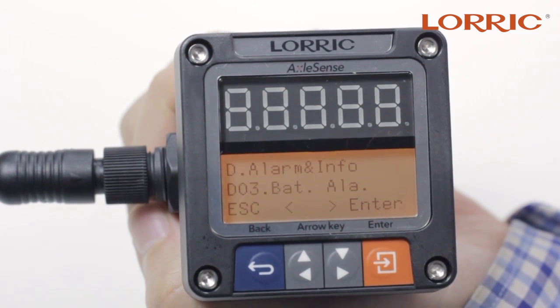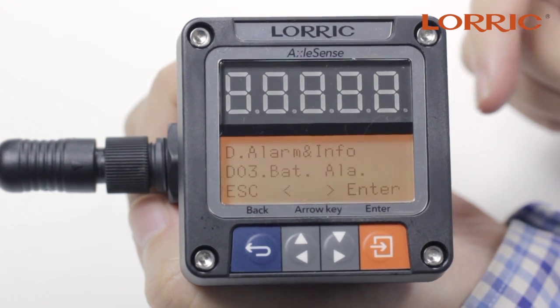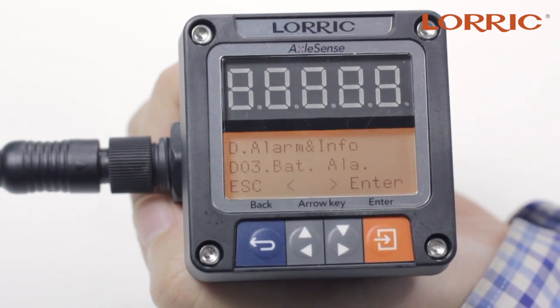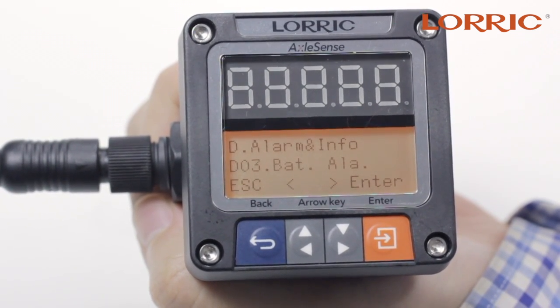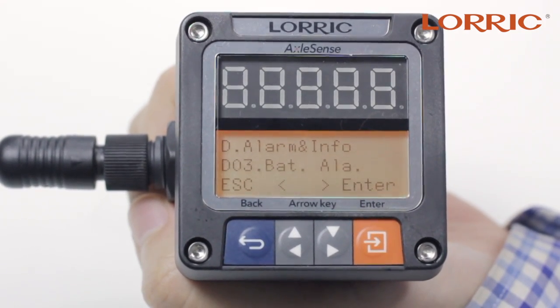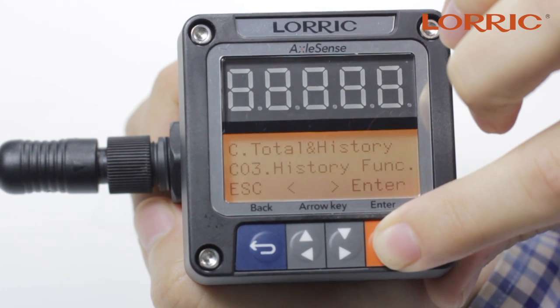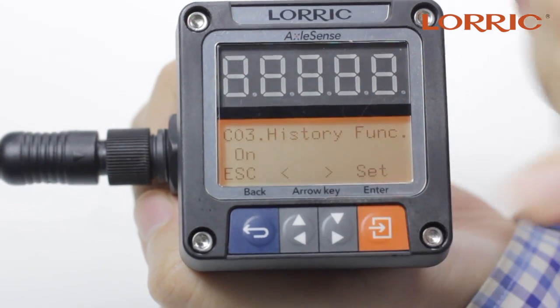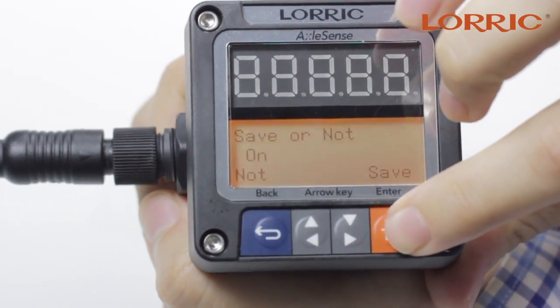If you actually have the battery in there, the screen will show the calendar function. On this calendar, you will put in today's date or any day that you want to begin recording the flow rate data. From that moment until 14 days later, it will record all the information for you. Click escape and go back to C, to the total history function. Click enter, go back to C03 — this is the history function. Simply click enter; it's already on. You can choose off or on, then set and save.